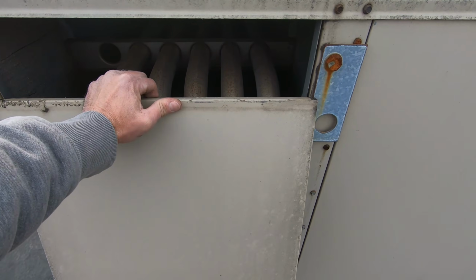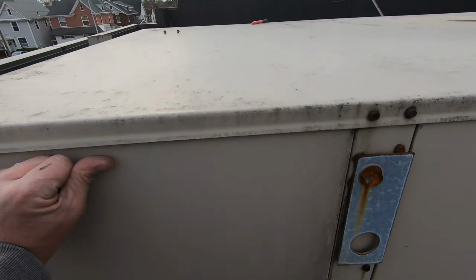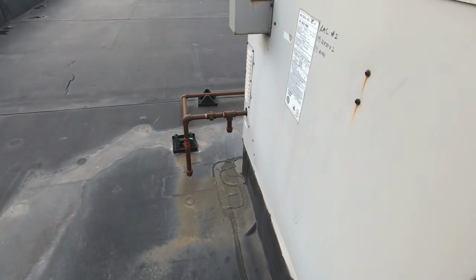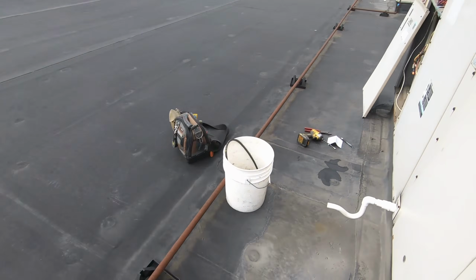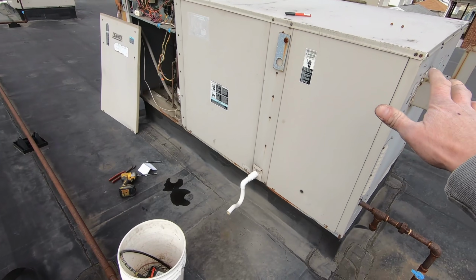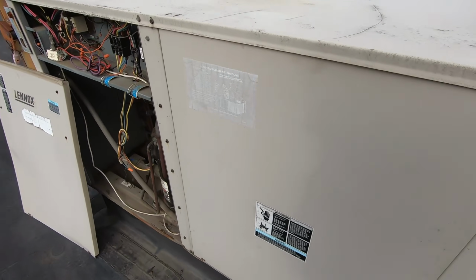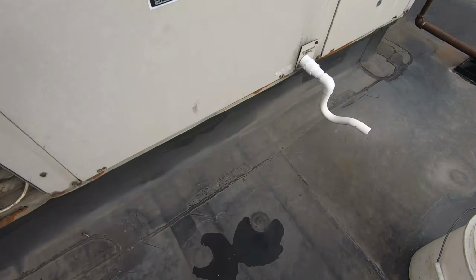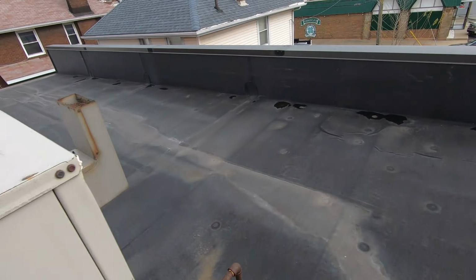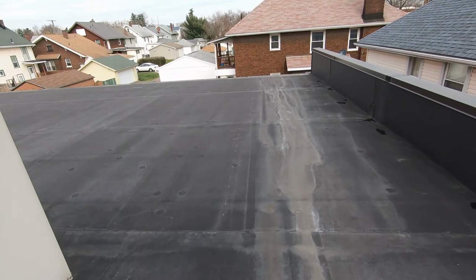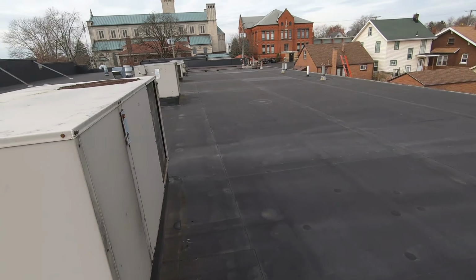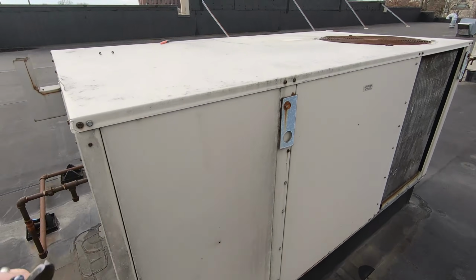I've got number 1 over there heating. We'll get all the panels put back on this one—it's disabled. I've got all the parts for the heat exchanger written up. I'm also going to include the pressure switch and gas valve, so just to cover my bases, we'll get all the heating parts: burners, limits, rollouts, flame sensor, igniter, pressure switch, gas valve.